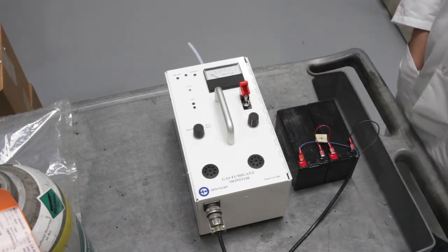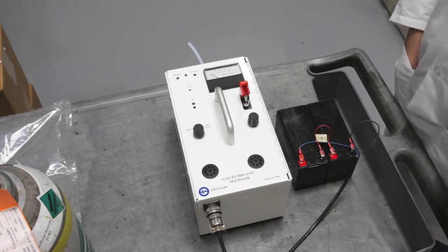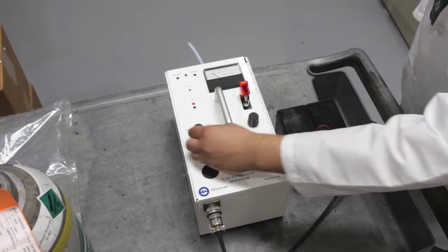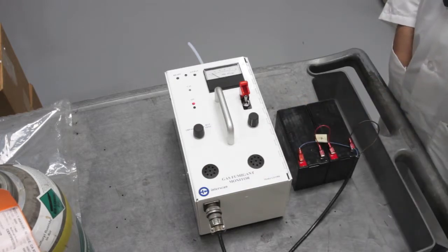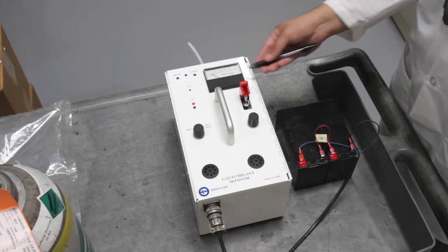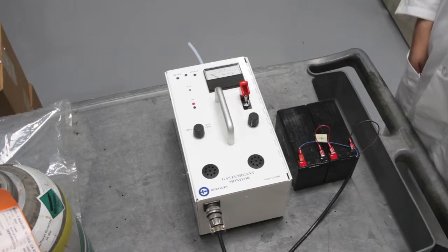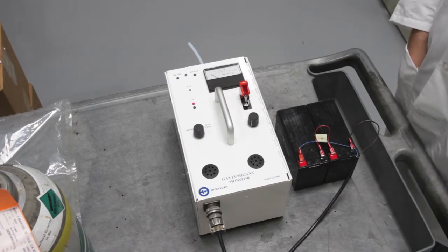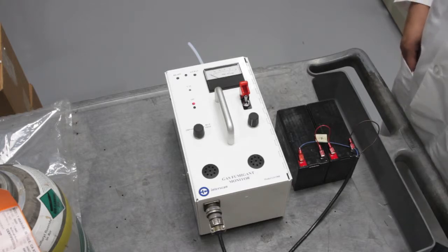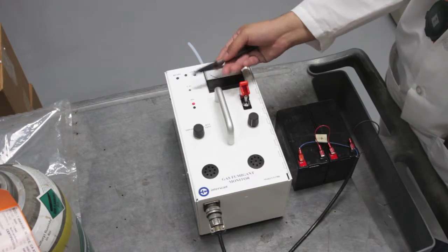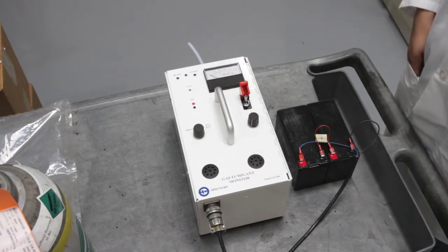In some cases, the monitor will indicate an upscale reading when powered on and drift downward while the monitor warms up. Upscale readings can exceed the full scale and do not necessarily mean there is a malfunction. The instrument is calibrated by introducing a known concentration of sulfuryl fluoride gas at 5 ppm and adjusting the span control to correspond to the known concentration of the gas.